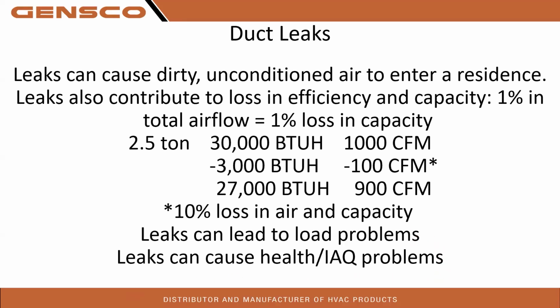Boy, I saved these people. They were having big issues and they had the duct board. And it was just a critter had gotten in there. So they had that insulation in their airstream for 4 years. She always had issues. We went in, tore out all that ductwork, replaced it with rigid metal, re-insulated it, put in a nice filtration system. And in 6 months, she had called me saying, thank you so much that we found that. She had been feeling much better. So that house was really affecting her health.